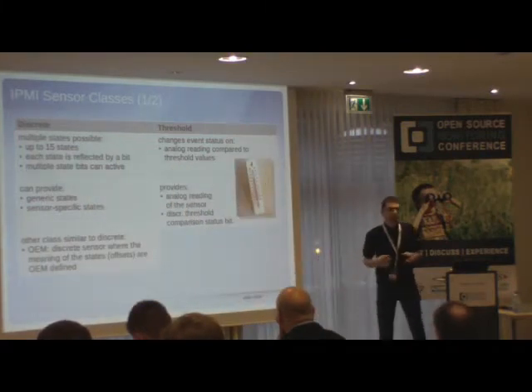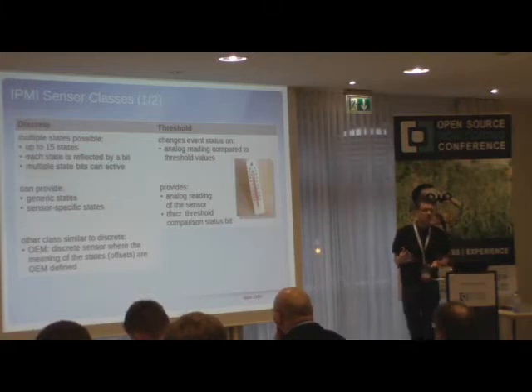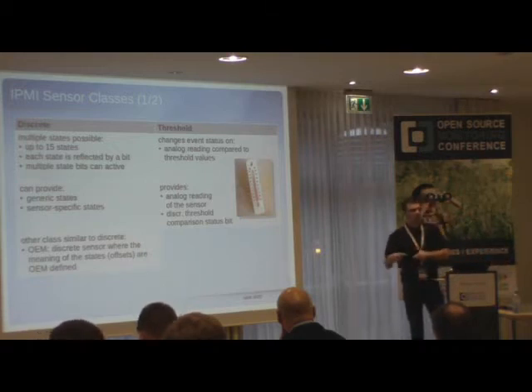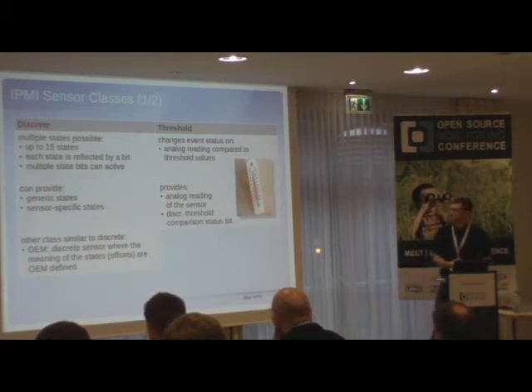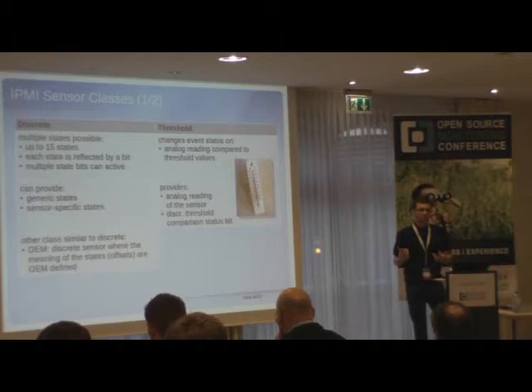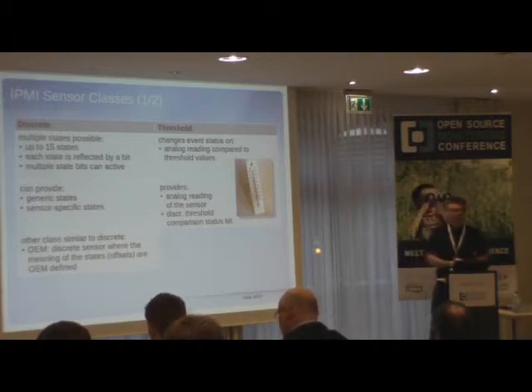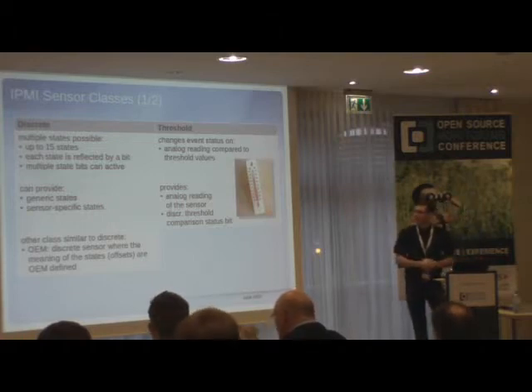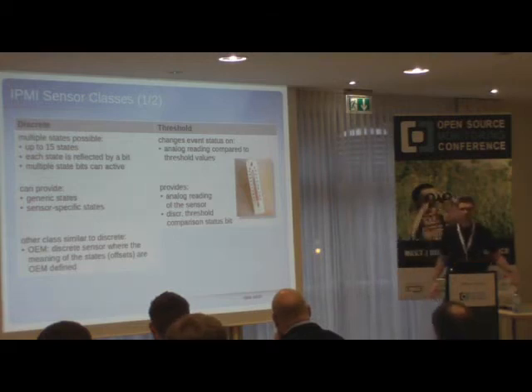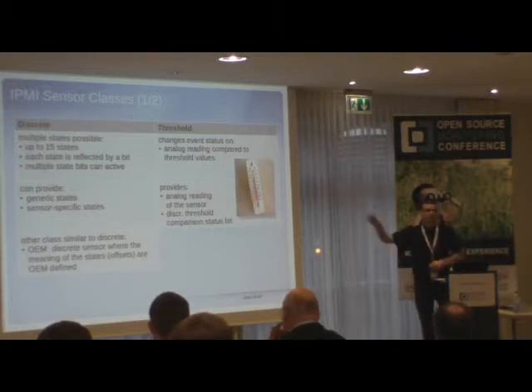In the IPMI standard there are also definitions for different types of sensors. For power supplies, the IPMI specification defines states like: the power supply is available, it has power on the inlet, and so on. For fan redundancy there would be other sensors. You can have generic states like available/not available, and sensor-specific states like 'power supply has power on the inlet' — which wouldn't apply to a fan redundancy sensor. You can also use OEM-type sensors for vendor-specific information.